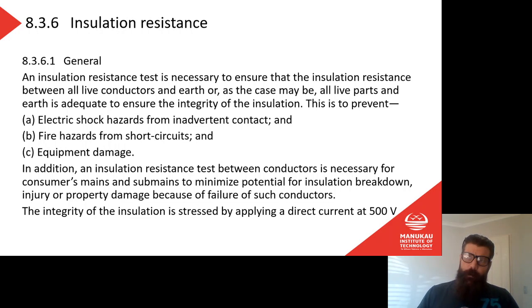So we use 500 volts. We have a special tester called an insulation resistance tester. It will output 500 volts, and that is the requirement. For anything that's going to be connected to a normal power supply, 230 volts, we must test it with 500 volts, with a 500 volt meter. Do not try and test insulation resistance with a multimeter. If there was a short circuit, you will find it, but if there's just a small fault in the insulation, you probably won't.